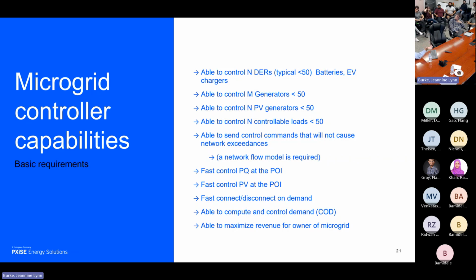Now, here's something that's also interesting, and Manny and I have talked about this for about 20 years also. This could lead to more sophisticated control by controlling the angle and the voltage. The state. Notice nobody's talking about state variable control in microgrids. State variable control is talked about theoretically in transmission. Very little is done in terms of control of state. We need state variable control all the way down to the POI of the microgrid. Now, I think in the next 100 years, probably that will happen. I won't be around here, but I've been pushing it since 1968. It's a way to control the grid as a state variable system, but I have not had any success whatsoever.